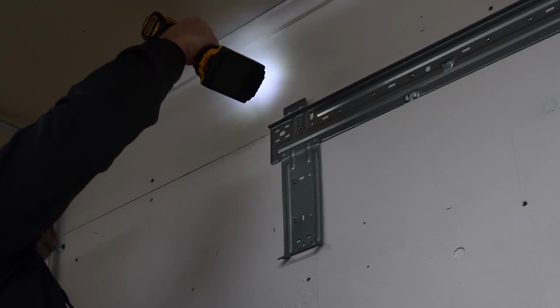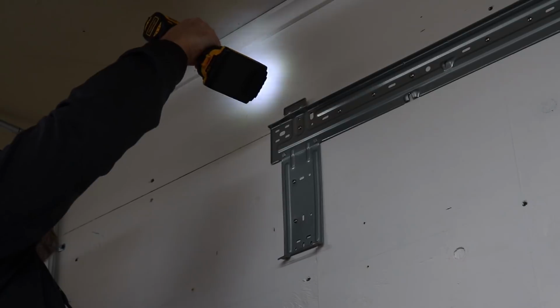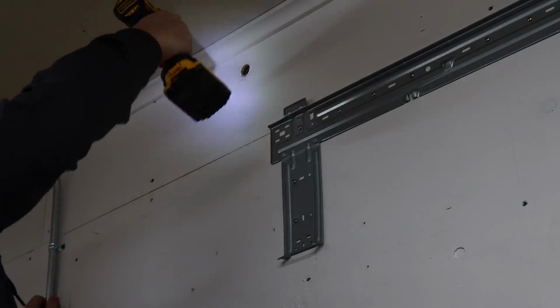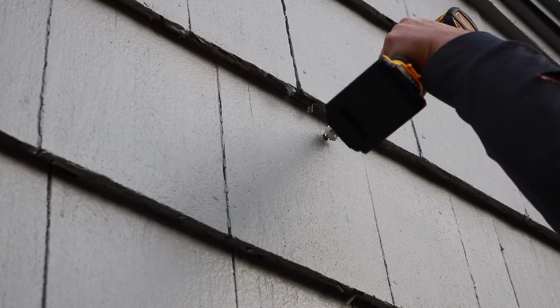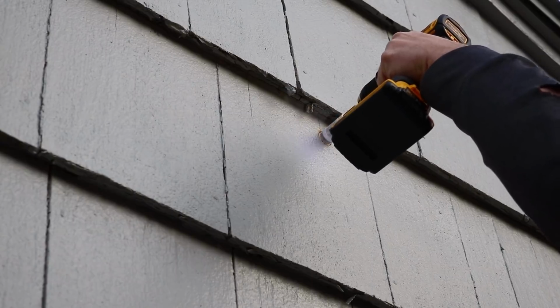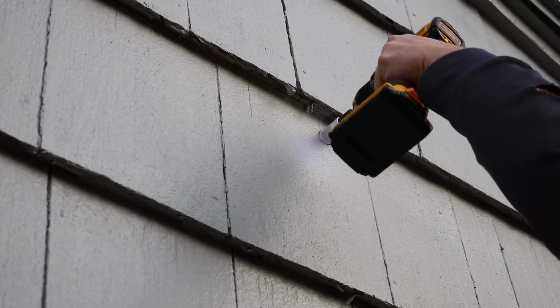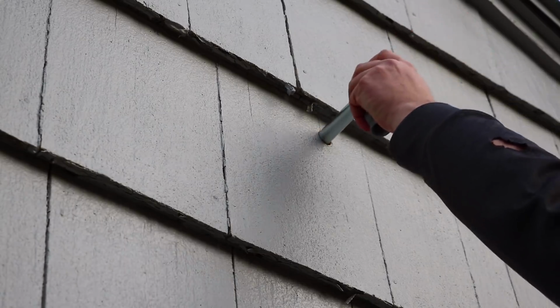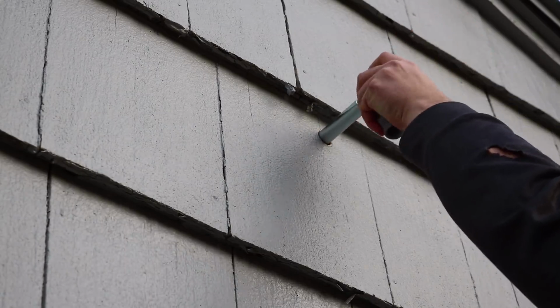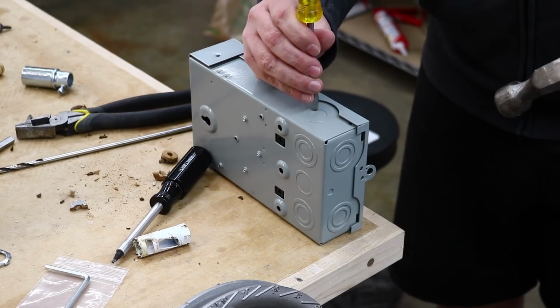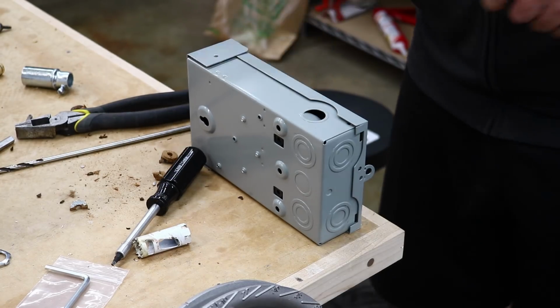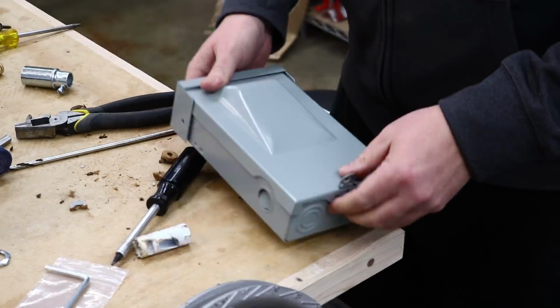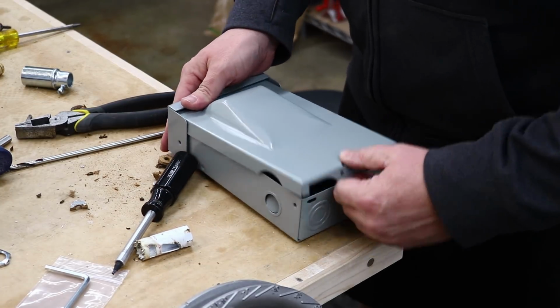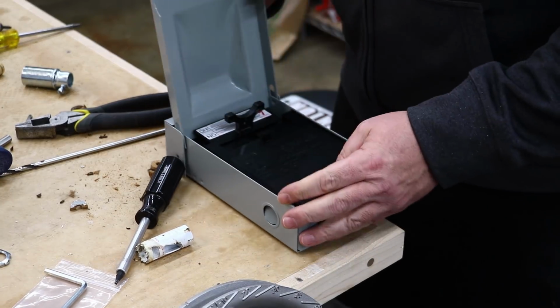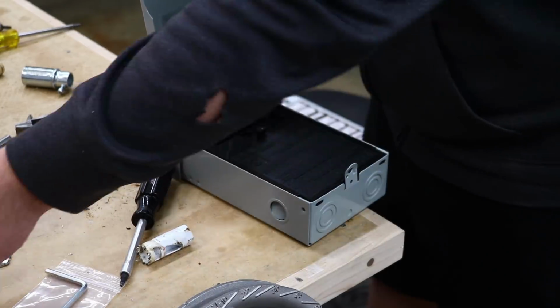I started out by drilling all the way through the wall with a long 1/4 inch drill bit, and then I used a 7/8 inch hole saw on each side of the wall to finish the hole. I then fed the L and galvanized nipple assembly through the wall in preparation of running the conduit down into this disconnect box. As far as I know, all HVAC units need a disconnect box within sight of the unit.